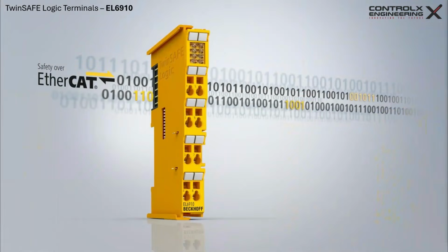Also available on this terminal are certified function blocks that enable the safe processing of analog values and thus the implementation of even more complex safety applications. This feature was not available on its predecessor, the EL6900, which only worked with Boolean values. With the EL6910, you are no longer limited to simple on-off safety inputs. You can safely process analog values such as pressure, temperature, position feedback, speed, or torque signals, pretty much any type of continuous value. This opens the door to more advanced safety functions.